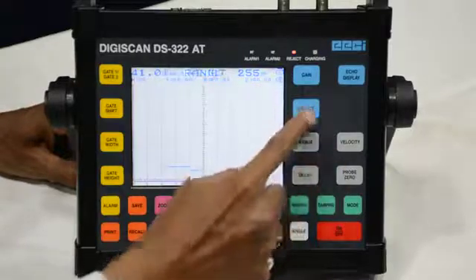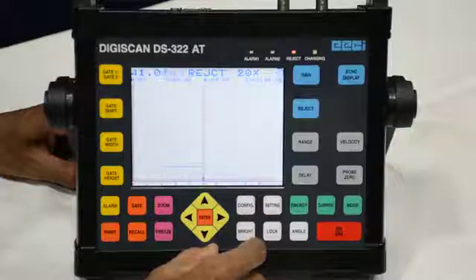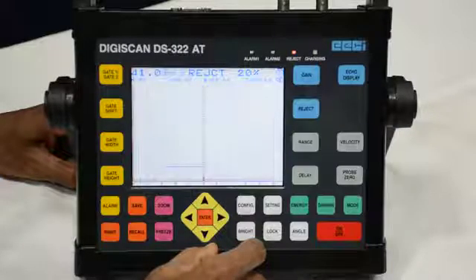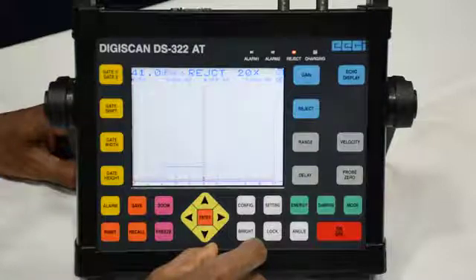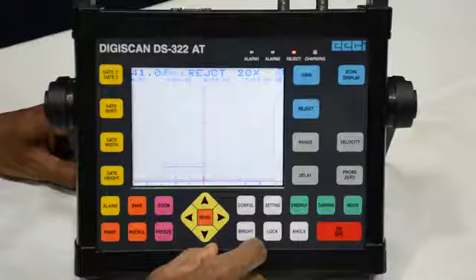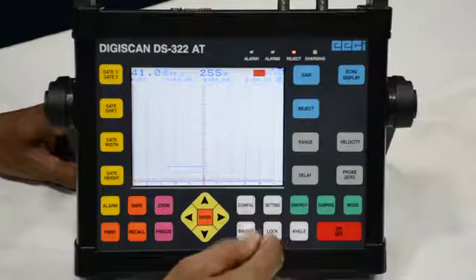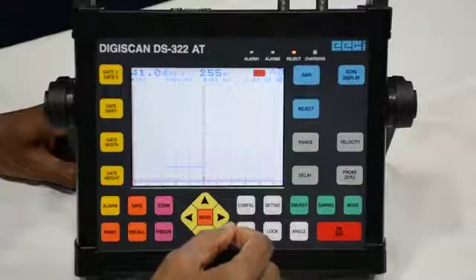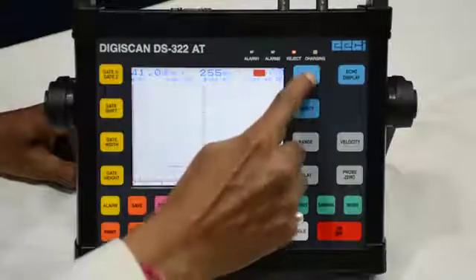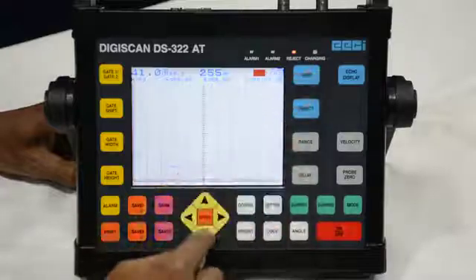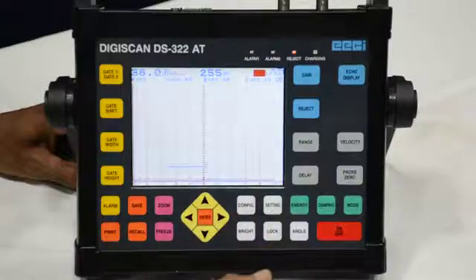Next is rejection. Rejection is a default value in USFD testing. Many unwanted echoes appear, and to suppress them we use this value. It should not be more than 20 percent. Next is the gain button. Gain is the intensity in decibels of the ultrasonic pulse we are sending into the object. We press this button and increase or decrease as per our requirement.